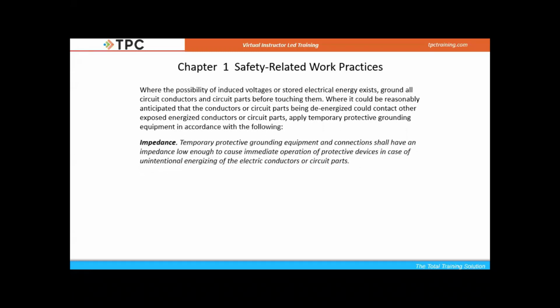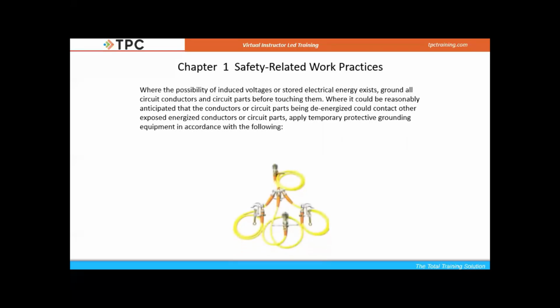Again, there's the ASTM standard, and they have to have a very low impedance. So it does allow the operation of our overcurrent devices. And so these are going to be pretty much straight copper wire inside. Again, we would be using a hot stick, and we would be a little bit of ways away from the equipment, hopefully, depending on the voltage, at least 3 feet away. And this is how we're always going to put it on.